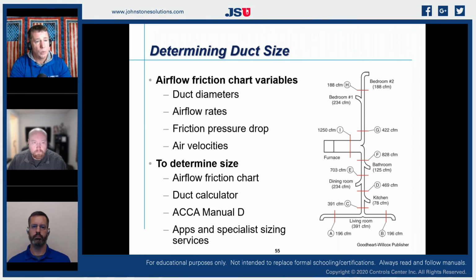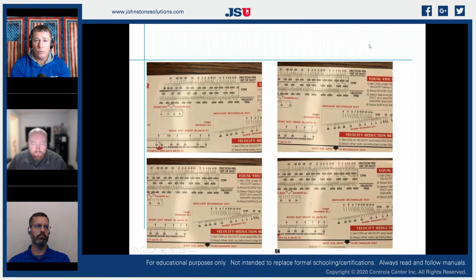I'm going to run square duct over, or I'm going to run round duct over, and we want to look at both of those. So I actually need 196 going to each one of those. So if I take my 196 at 0.1, that would be our top left one. I can do, if I'm doing rectangular or if I'm doing round, so there's 196 at 0.1, it's pretty close to there. You see my 2 options? I can run either an 8-inch round, or that says an 8x6, but we don't stock an 8x6, so I'm going to end up with an 8x8.